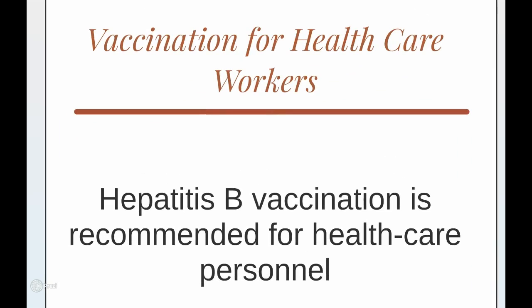Hepatitis B virus, or HBV, is a highly infectious and environmentally stable blood-borne pathogen. It can be transmitted by medical equipment contaminated with blood that is not visible to the unaided eye. Percutaneous exposure to HBV occurs as a result of assisted monitoring of blood glucose and other procedures involving instruments shared between persons. Lapses in infection control during assisted blood glucose monitoring that have led to HBV transmission include multi-patient use of fingerstick devices designed for single-patient use, as well as inadequate disinfection and cleaning of blood glucose monitors between patients.